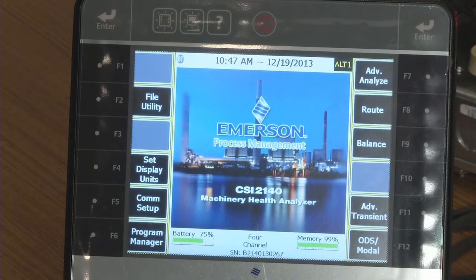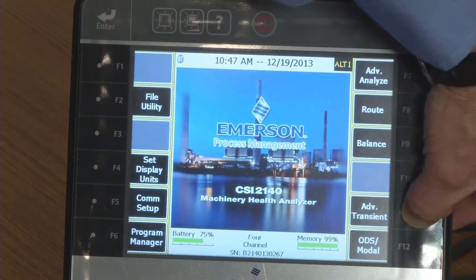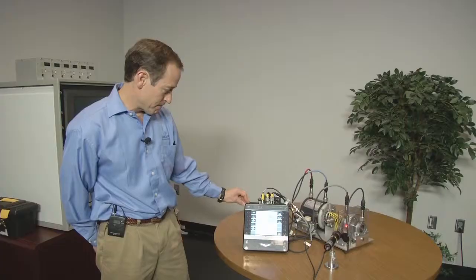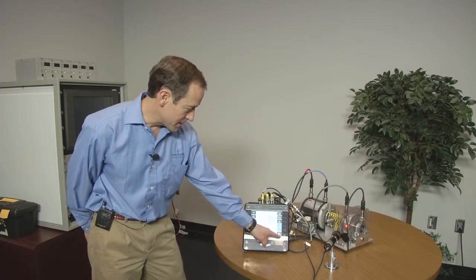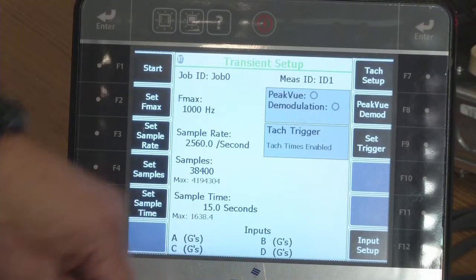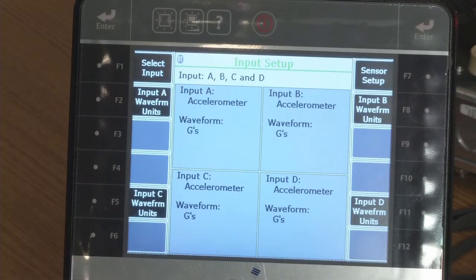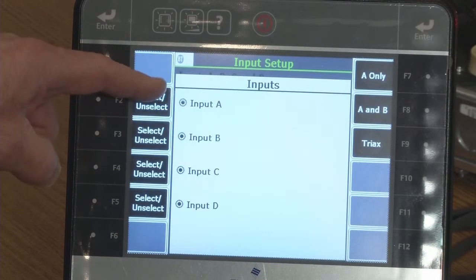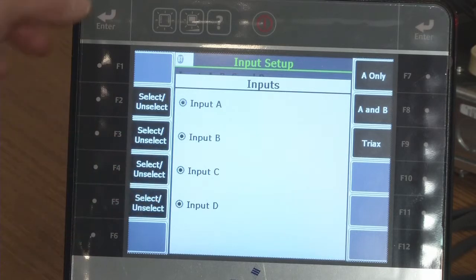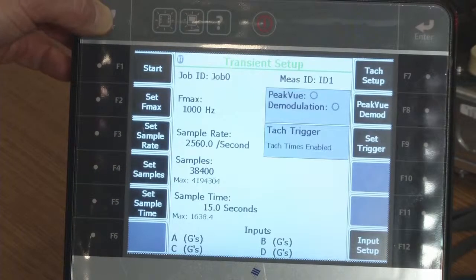To begin transient analysis, from the home page of the 2140, click F11 to open up transient, and the first thing you want to do is verify that you have all four sensors programmed to collect data. From the input setup, I see that I've got all four accelerometers selected. I see that I'm going to take 15 seconds of data, and I'm going to have an Fmax of 1000 Hz.